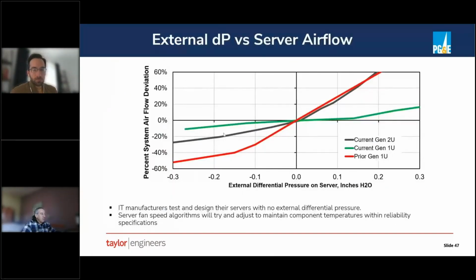This is a graph showing what a server can handle in terms of external pressure. If you put pressure on the server, it's going to flow more air than it was designed, right? At zero, there's no deviation in what the airflow is going to be. If you put more pressure on it by keeping your aisle positively pressurized, that's fine. Flowing more air through the server is not a problem. The problem is over here, where again, the Bernoulli effect creates a negative pressure in front of the server. Then as the negative pressure gets more negative, if you will, you lose airflow.